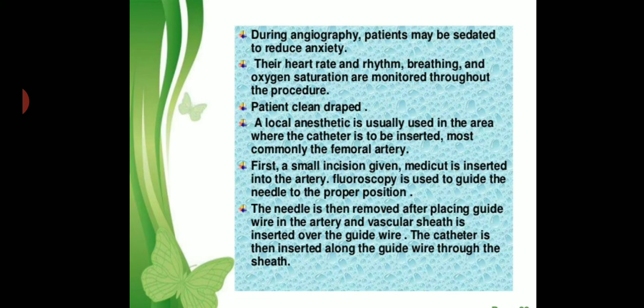Medicut is inserted into the artery. Fluoroscopy is used to guide the needle to the proper position. The needle is then removed after placing a guide wire in the artery and a vascular sheath is inserted over the guide wire. The catheter is then inserted along the guide wire through the sheath. When the catheter is in correct position, the wire is pulled out and dye is injected through the catheter. Images are acquired during contrast injection. Injections can be made directly into the artery of interest.